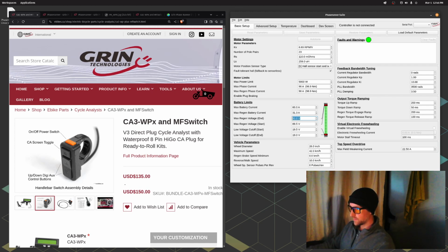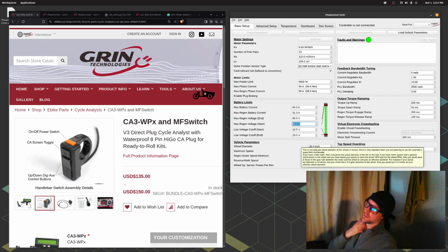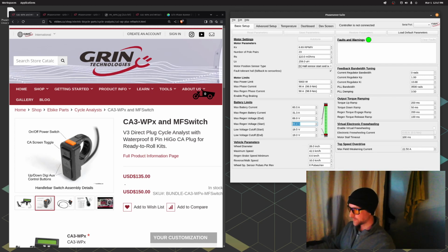89.9 and 89.4 or something like that is probably good, because there are components inside the Phaserunner that are only rated to 90 volts. So you want to keep it in check. A 21S battery goes up to about 88.2 volts, so if my battery goes above 89 volts, that's kind of a bad situation. So maybe 89.5 and 89 on 21S.